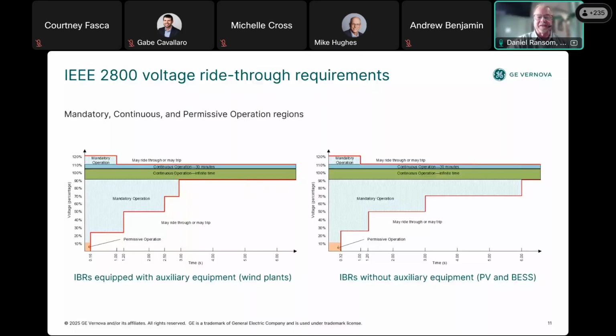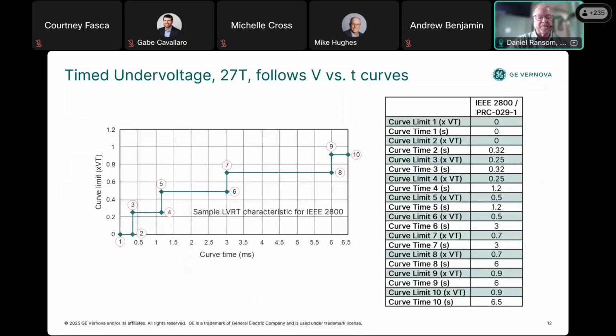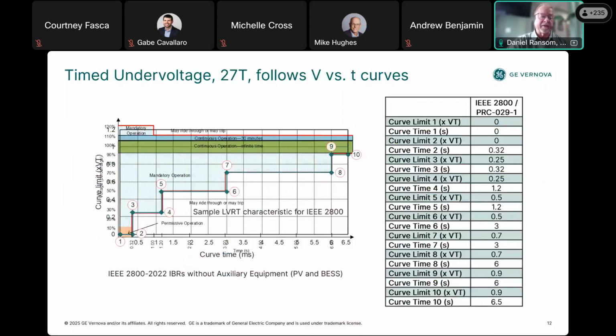Okay, thank you, Dan. The next one we have, they're asking, is the 27T element based on single phase or three-phase voltages? Configured to what you have to measure. I'm just going to pull up the slide here. Now it's working. So let's look at the PRC-029. The 2800 and the 29 are pretty close. They only vary in the overvoltage region, but mostly this element works in the undervoltage region. So yeah, it'll help the IBR plant maintain limits that it needs to see. And it's measuring at the point of applicability, not way upstream where the controller is.